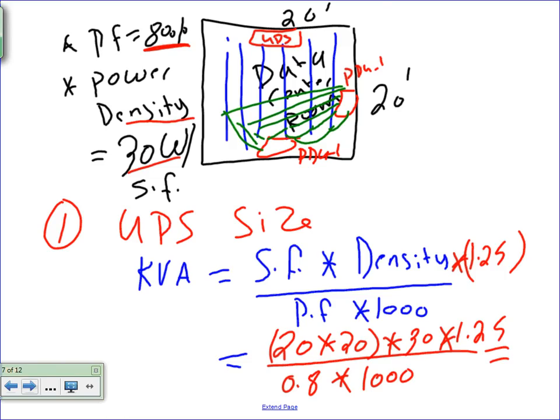18.75. 18.75. A second? 18.75 kVA. Do I have a second? Second. Okay. 18.75 kVA. Any question, guys, about this? There are two ways of doing it. You do it this way, that's the engineering way, or the other way, go to every single server, find the input amps on the server, multiply by the voltage, multiply by 1.25 for continuous load, and add them up.